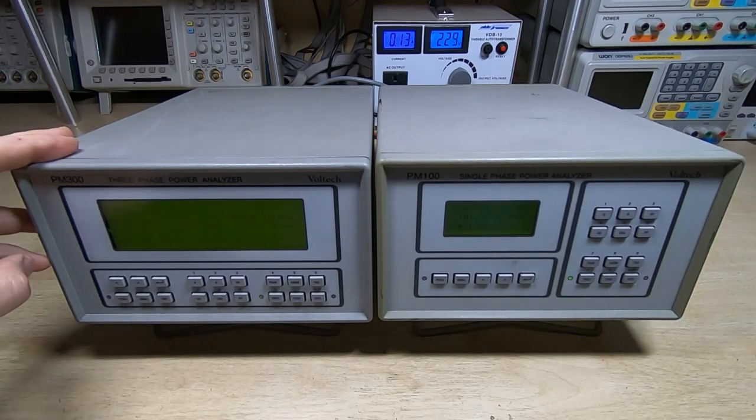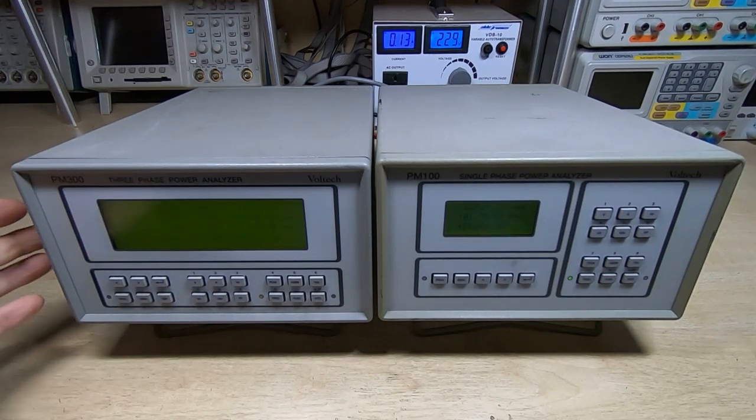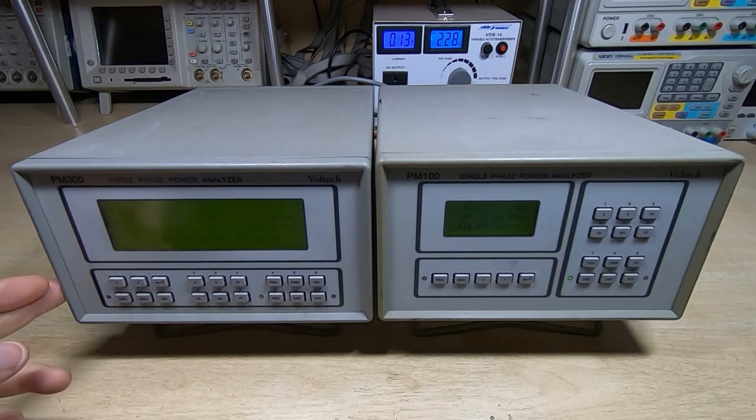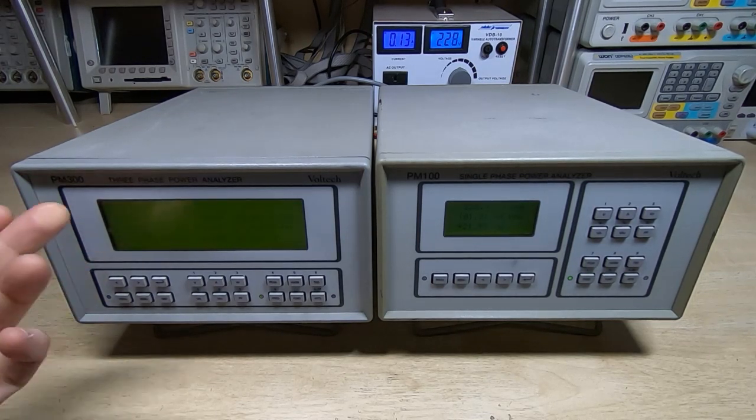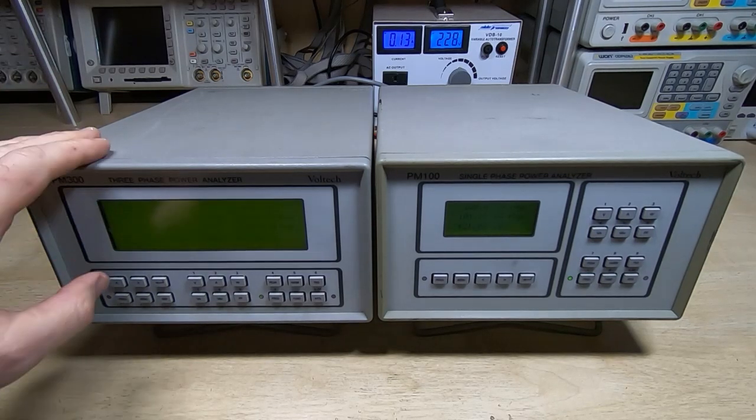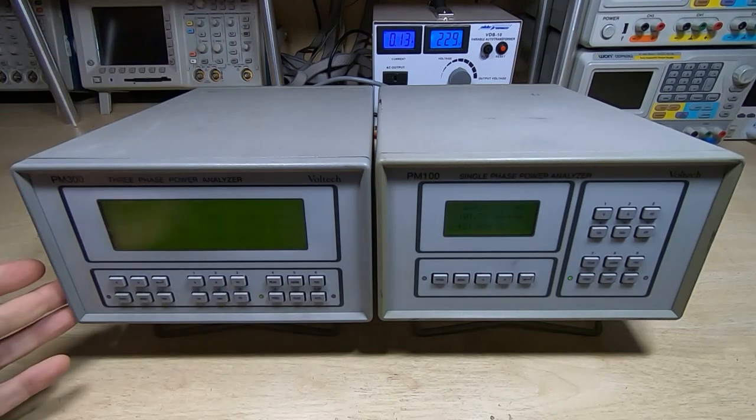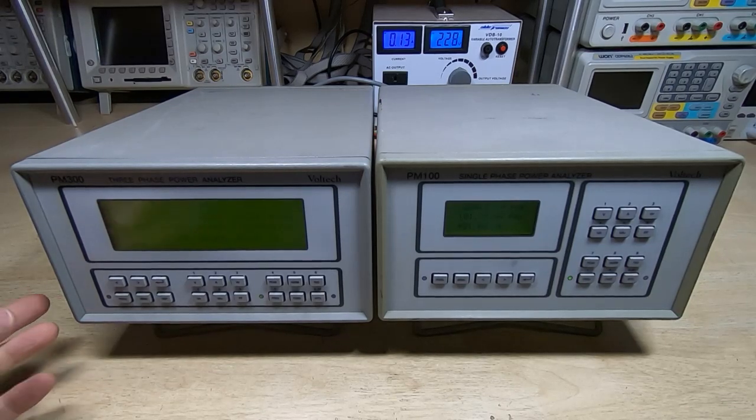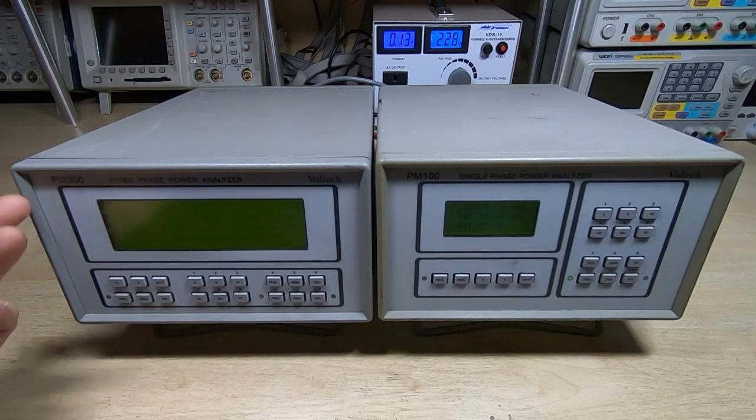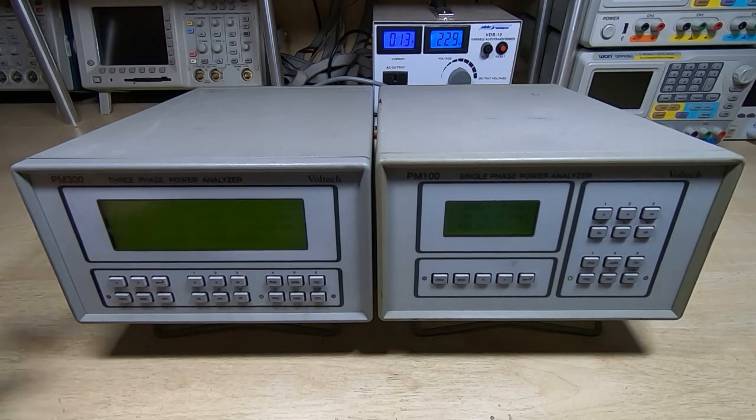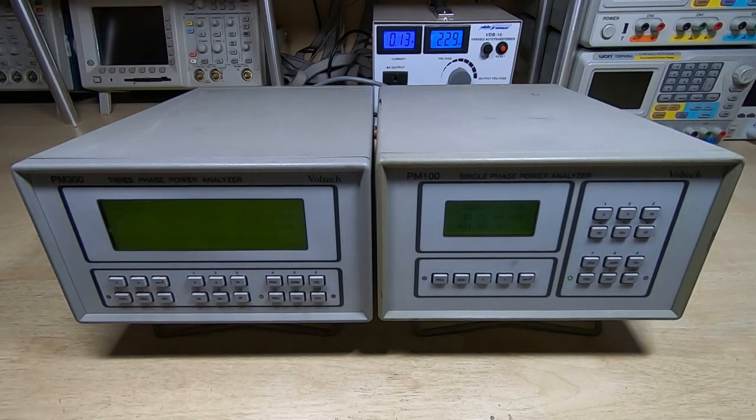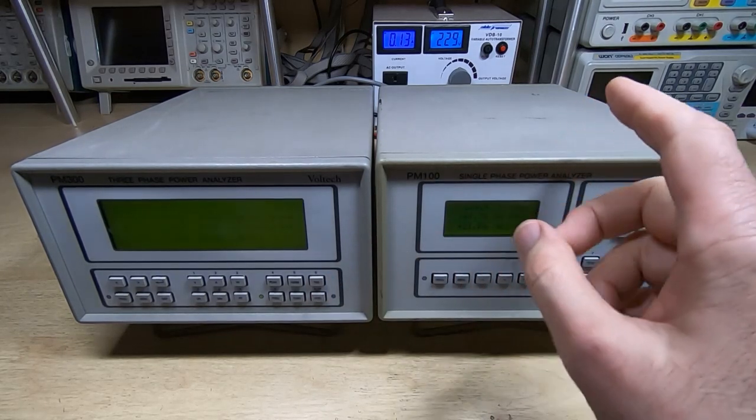In a recent series of videos I repaired this PM300 power analyzer. In fact, all I did was calibrate it. It was coming up with a calibration error when it was powered up, it just needed calibrating. But what I did was completely strip it down, I cleaned up the fan which was making a horrendous noise, cleaned up the entire instrument, reassembled it, recalibrated it again, and now it's working fine.